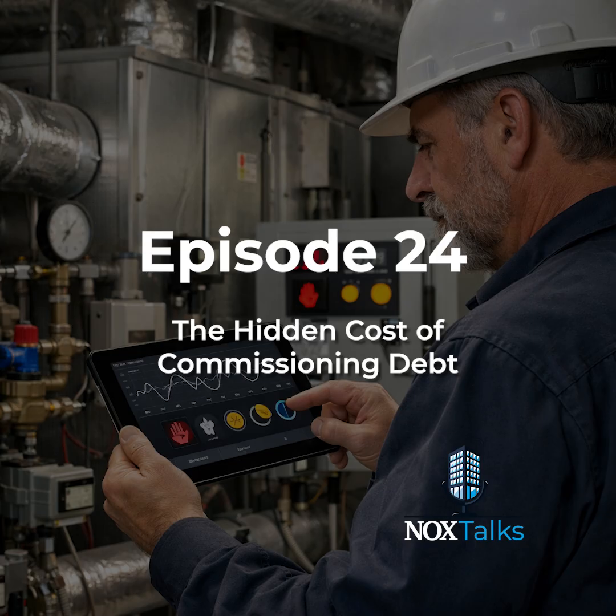And here's another fun fact. Large-scale Berkeley lab research found existing building commissioning still tends to pay back fast, with a median simple payback of about 1.7 years. Depending on program type, median primary energy savings range from about 5 to 14%. So when someone says tuning is soft savings, the data says otherwise.